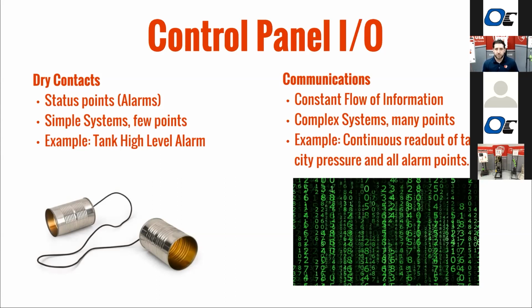A lot of these are tucked away in basements or out in parking garages, so they're not going to see that the panel lights are out in passing. So it's good to get that feedback through the building automation. And then the communications are going to use the typical protocols, BACnet, Modbus, things like that, to give that constant flow of information, the actual readout of what the sump level is, things like that. So a lot more information can flow back and forth via communication than dry contacts. We can do communication with the Elite series and then the dedicated controls. When you're using a relay logic type panel, you're going to be typically limited to the dry contacts.